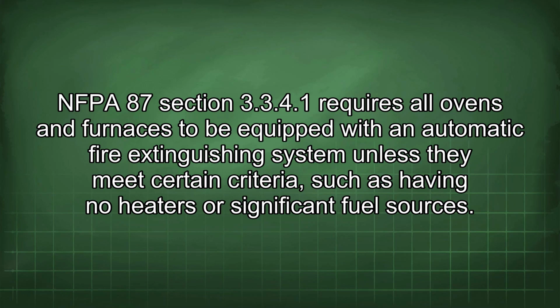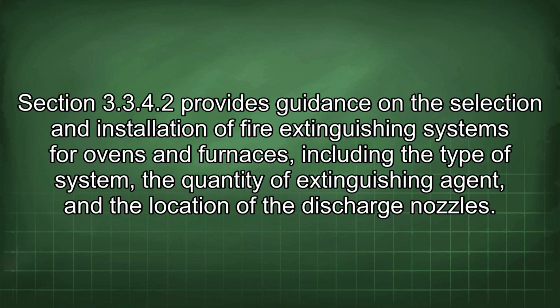NFPA 87 Section 3.3.4.1 requires all ovens and furnaces to be equipped with an automatic fire extinguishing system unless they meet certain criteria, such as having no heaters or significant fuel sources. Section 3.3.4.2 provides guidance on the selection and installation of fire extinguishing systems for ovens and furnaces, including the type of system, the quantity of extinguishing agent, and the location of the discharge nozzles.